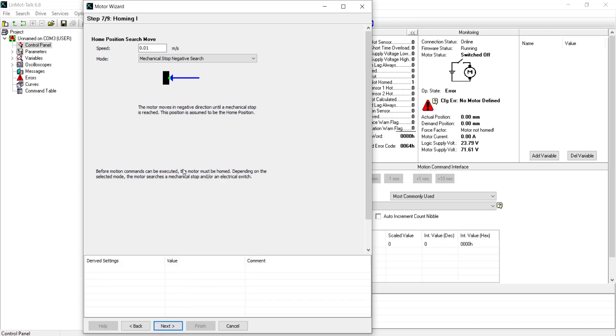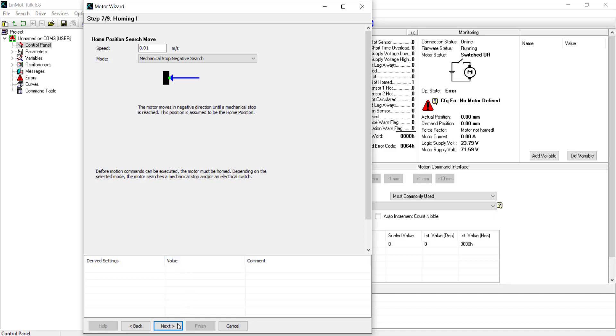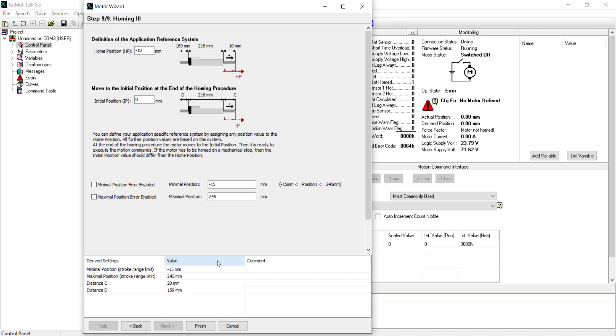The default homing mode is mechanical stop negative search, in which the motor travels in the negative direction until it hits a hard stop, which it detects by observing a spike in current. Several other homing methods can be defined in this step. The driver uses the parameters defined in this step in order to determine the alignment of the slider within the stator at the home position. For mechanical stop negative search homing, these settings reflect the distances when the motor is at the hard stop. These settings can be left as default unless if tooling is attached, changes the position of the hard stop, or an alternate home routine is used.